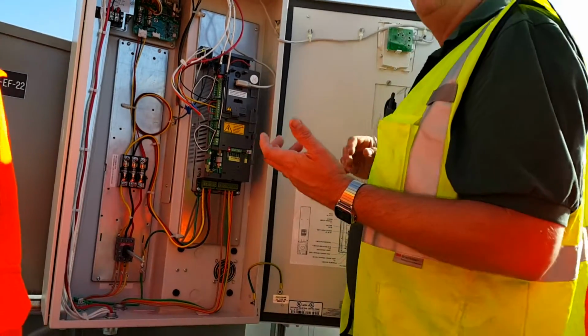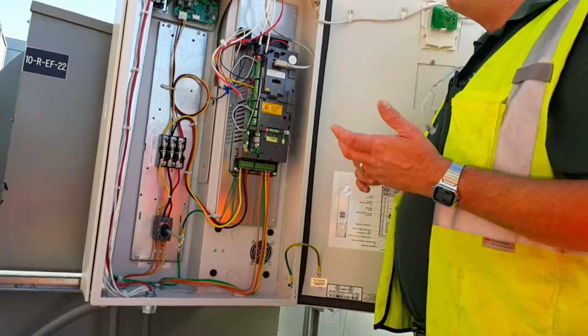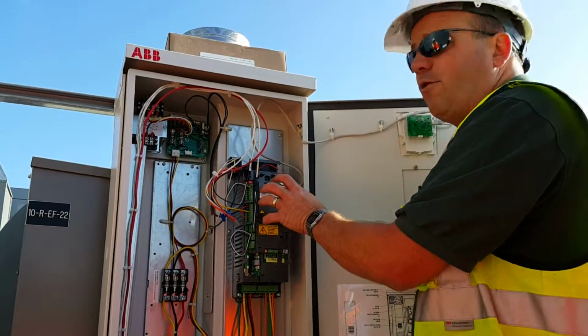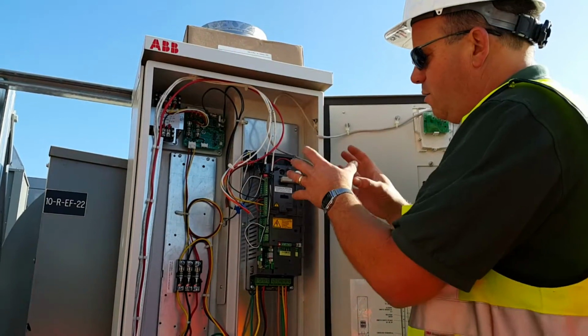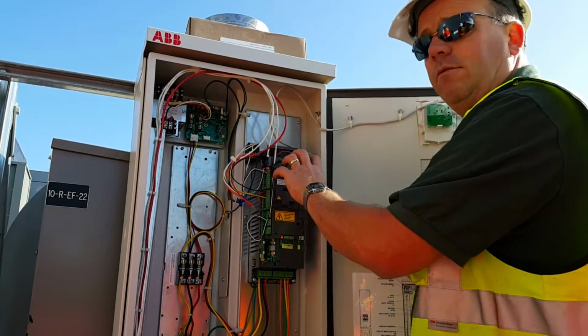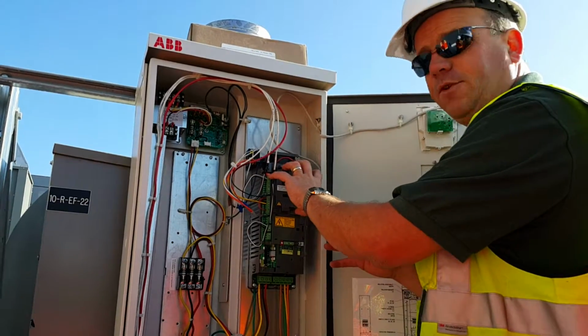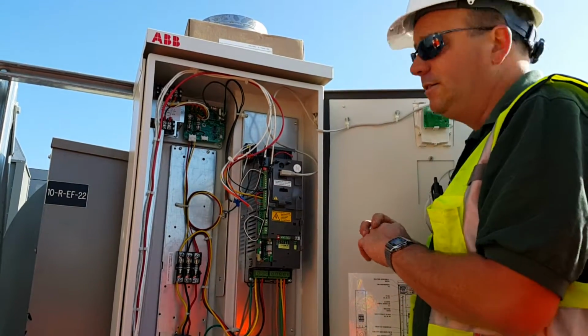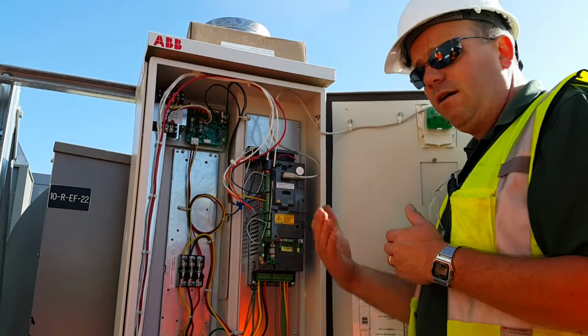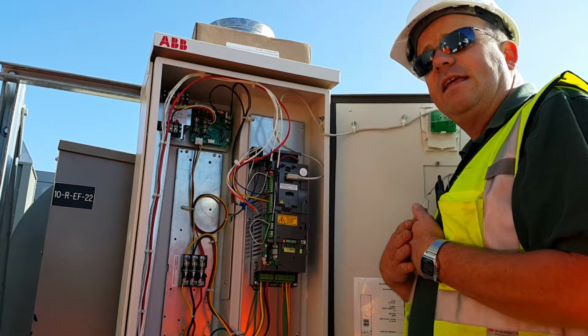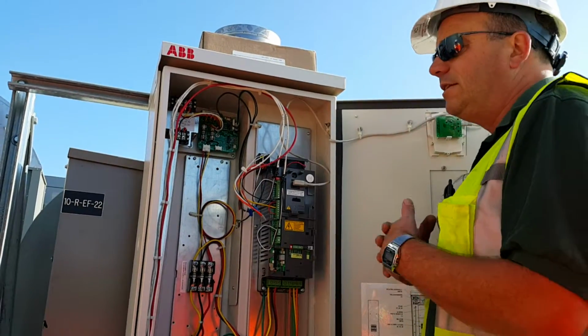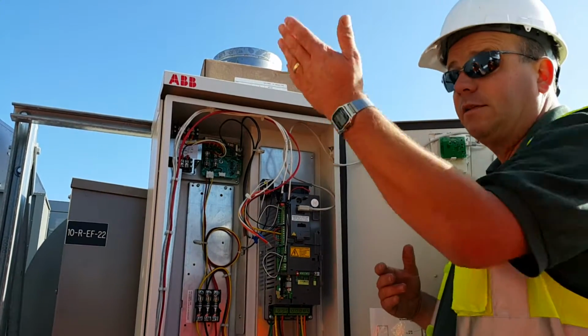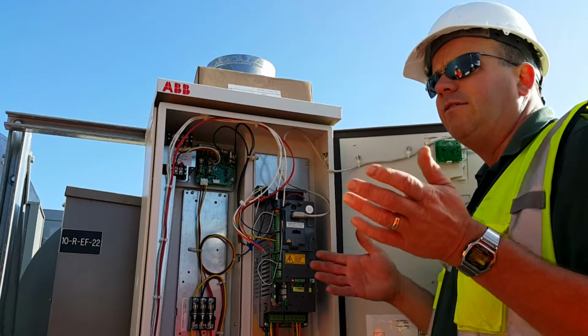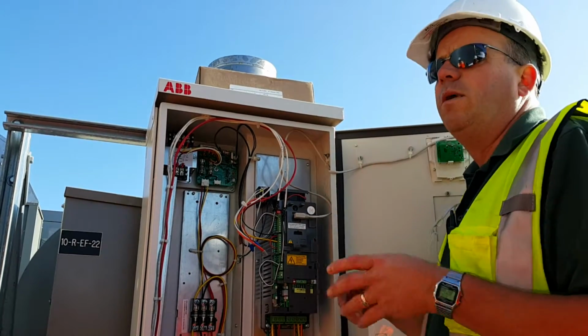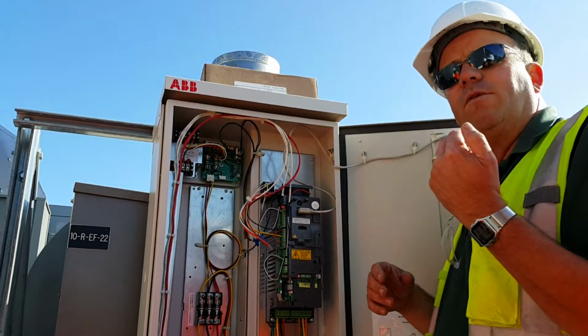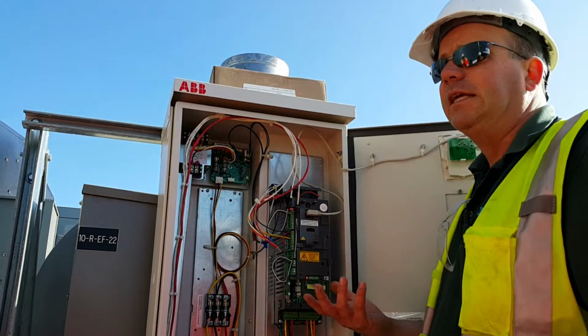Like, you can mount is it a remote or something? There's a couple things. You can mount them, well, like this one's mounted not on the drive. Like you can see some of the drives inside here, where it's just a drive on the wall. Yeah. It'll actually mount, there'll be a cover on this so that it mounts right on the drive. Then you can take it and mount it other places. You can also take a copy of the program, upload it into that keypad and bring it to another drive. Let's say you have 10 drives on a wall, they're all similar. Like somewhere inside here, you got like 3, I'd say right next to each other. And you change one out, you can take one, upload it from that one, download it into the drive. It's like a memory stick.